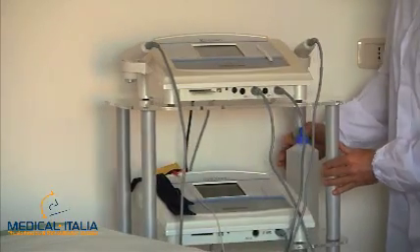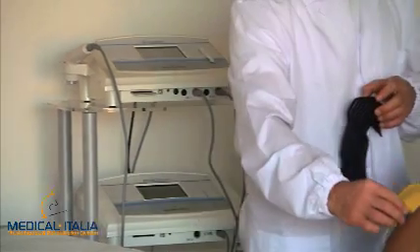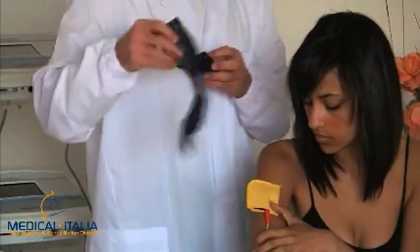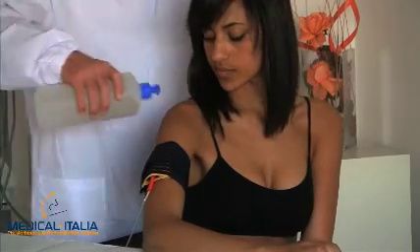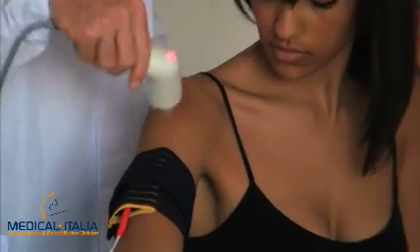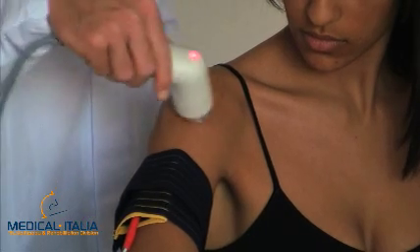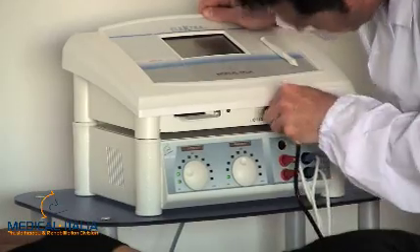At this stage you will work only with channel one of electrotherapy. Place the positive red electrode close to the area to treat; the ultrasound probe will be used as the negative pole. Simultaneously, you will have both the electric pulse and the ultrasound treatment. After starting, the intensity of electrotherapy is increased as in a standard treatment.